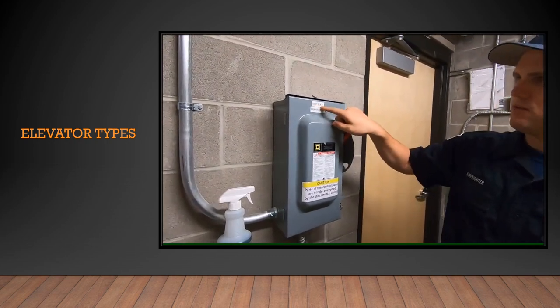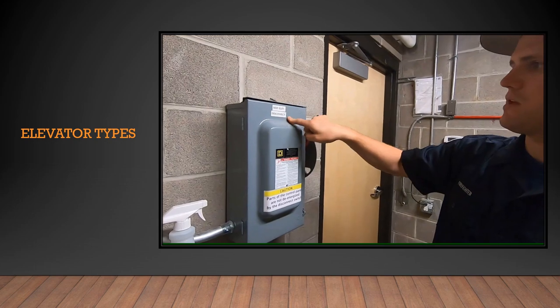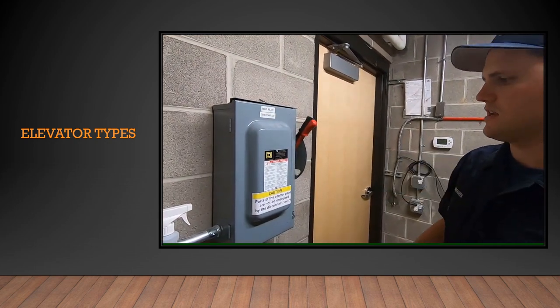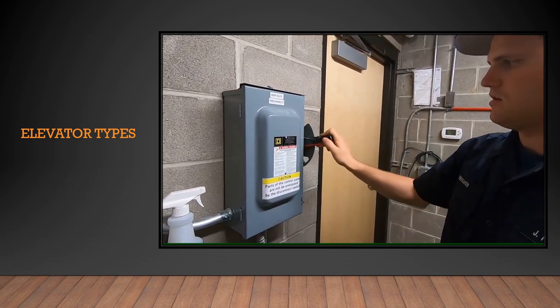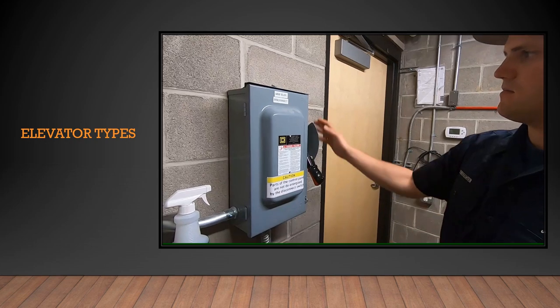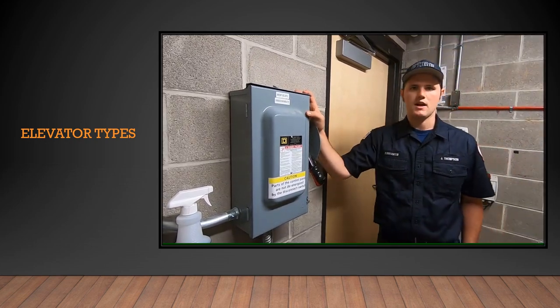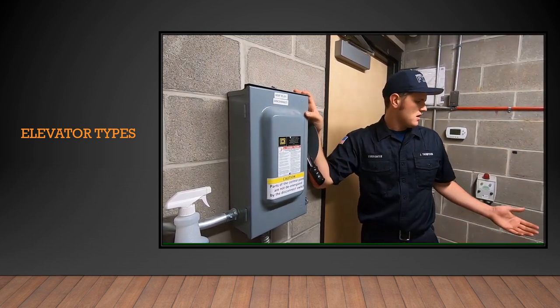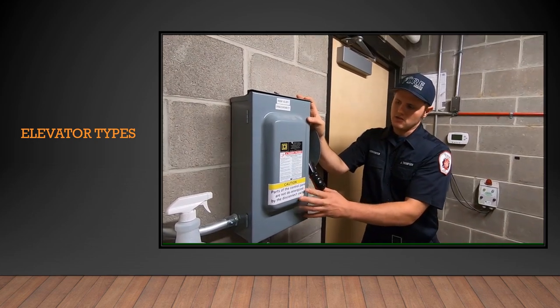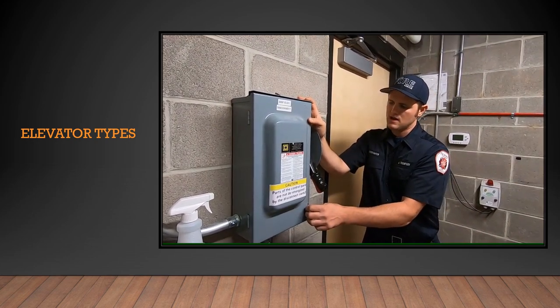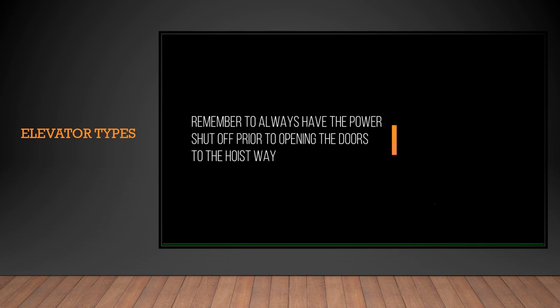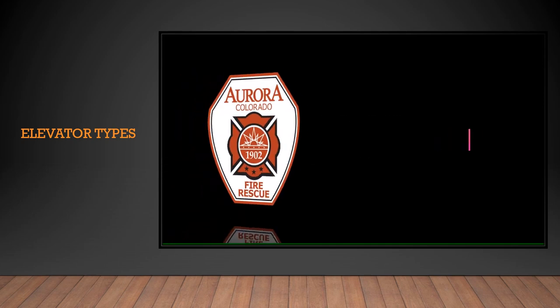The elevator power disconnect will be labeled. In this building with one elevator, it's labeled 'MDP elevator disconnect.' This is the major power source that needs to be shut off — it's a standard pull-down shutoff. If it's going to be an extensive rescue and you have a machine room, keep a firefighter here with the power shut off, or use your lockout tagout kit so nobody can turn it back on. Remember: power to the elevator motor must be off prior to opening the doors to the elevator shaft. This is important for the safety of the occupants and the safety of our firefighters.